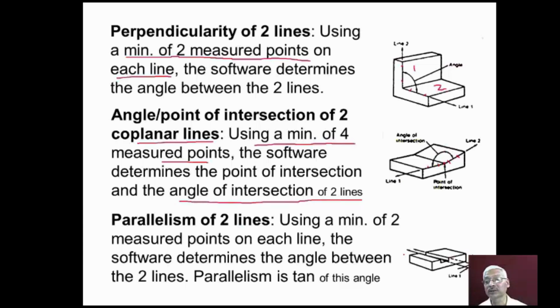You can see here we have line 1 and we have line 2, and using the minimum of 2 measured points on each line. So we should select 2 points on line 1 and 2 points on line 2. That means total 4 points we should give. Then the software determines the angle between these two lines, then the parallelism is tan of this angle.